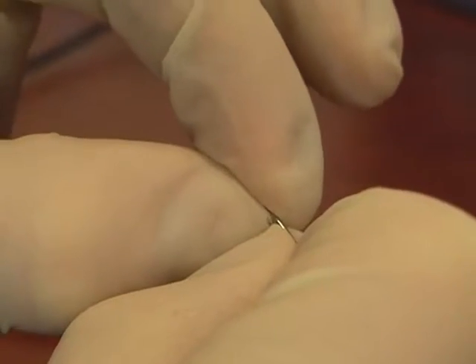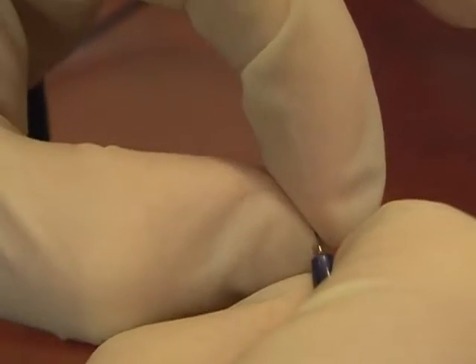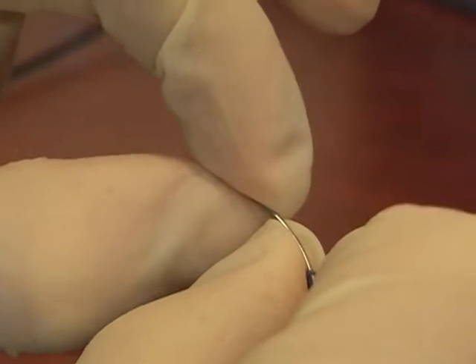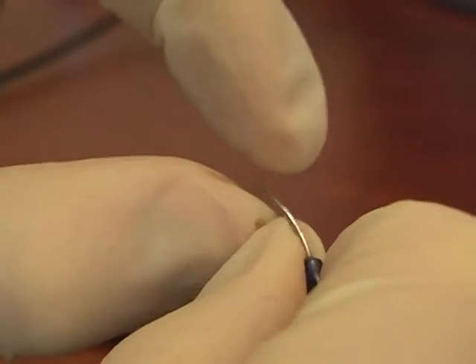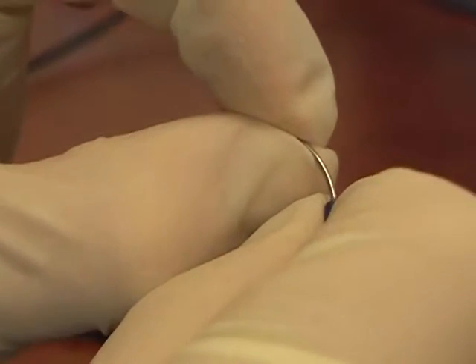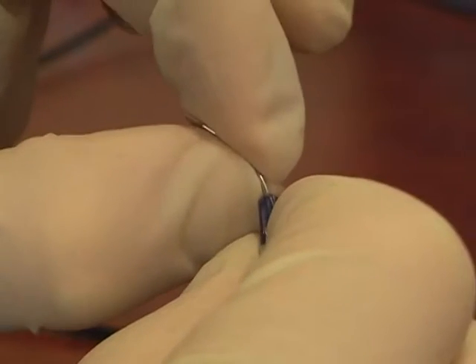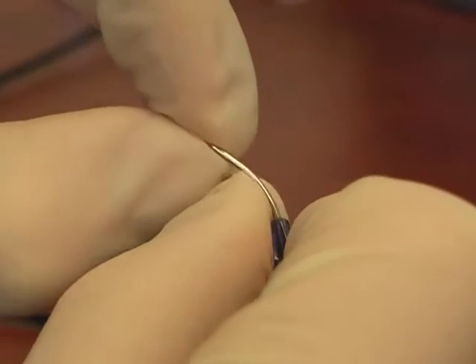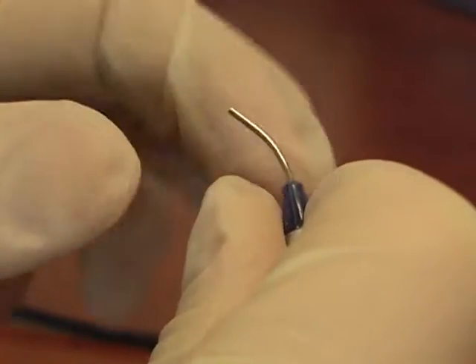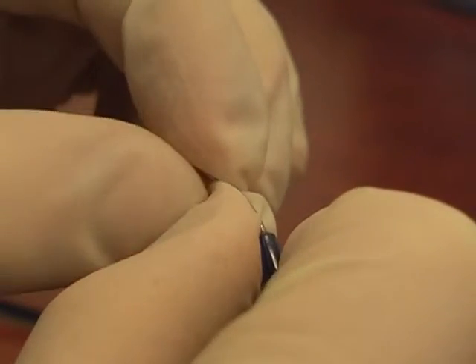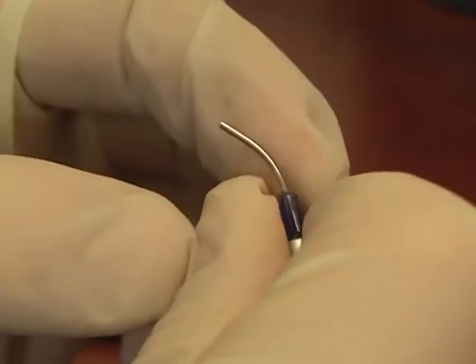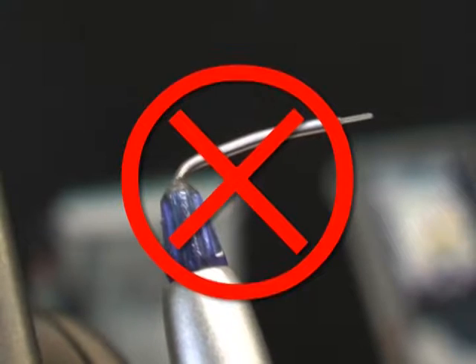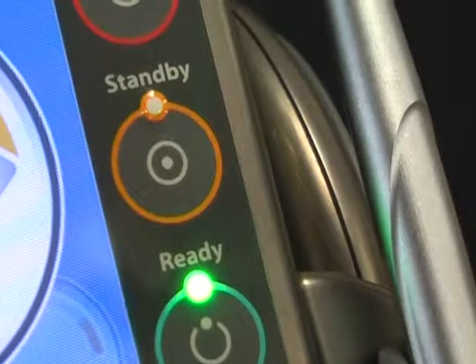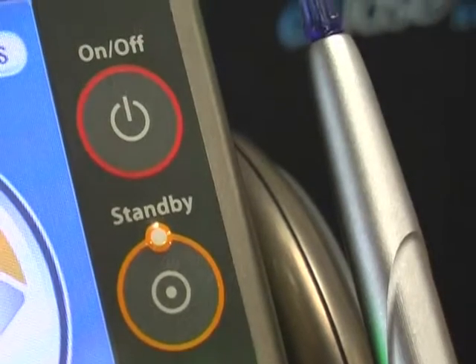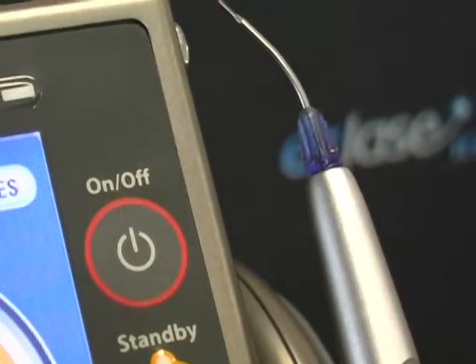The tips are designed to be able to be bent to create an angle for better access. To do this, hold the tip between fingers and thumbs at both ends of the metal part or the cannula and gently bend the cannula of the tip until you reach the desired angle. It is important to create the bend in the middle of the cannula and not at the junction of the plastic coupling and the cannula. The tip can be bent to 90 degrees, but the curve of the bend must be gentle and not a tight angle, which might break the fiber inside the metal cannula.